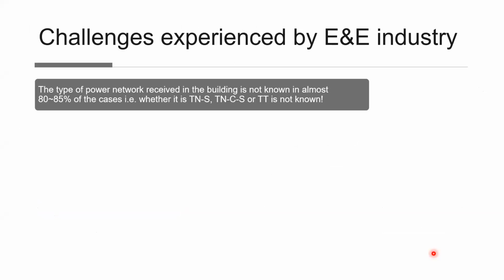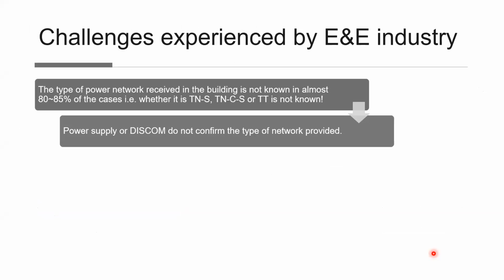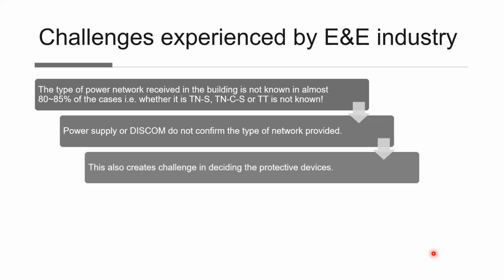What are the challenges we face today in the elevator and escalator industry? The type of power network received in the building is not known in almost 80 to 85% of the cases. That means we don't know whether it is a TN-S network, TN-C-S network, or a TT network. When we talk to the customers or the power supply or the discom companies, we do not get an answer as to what type of network is provided to the installations. This also creates a challenge in deciding the protective devices. So if it is a TT network and somebody assumes, because there are 5 wires coming to the elevator installation, that it's a TN-S network, this could lead to a mistake, because in the TT network, we need the RCD type D as a mandatory requirement. And this could lead to violations.